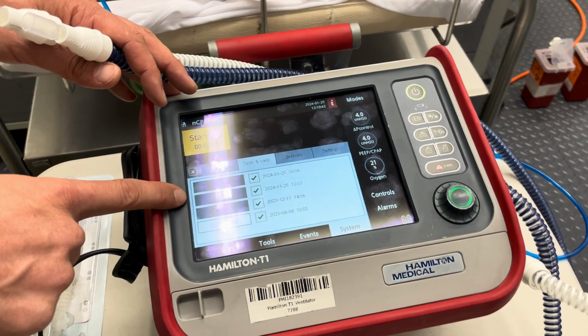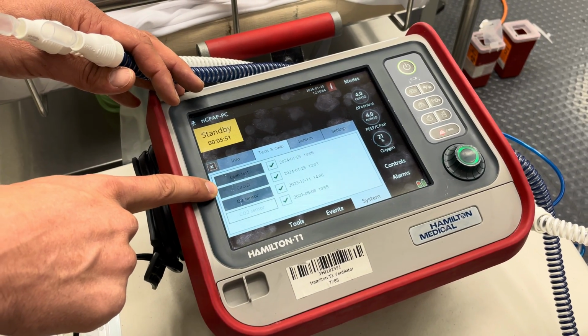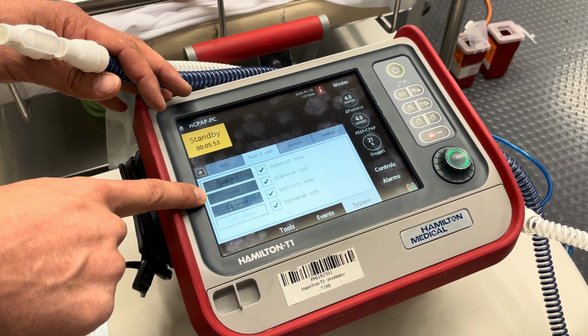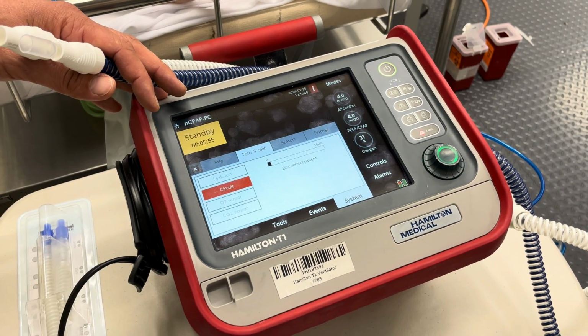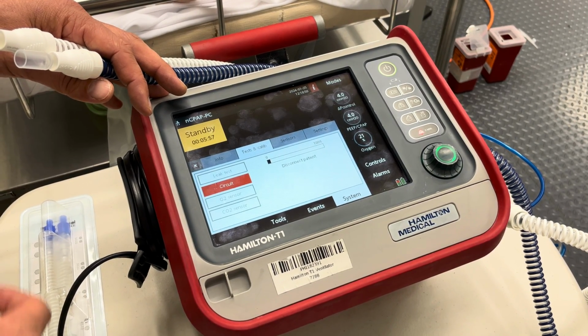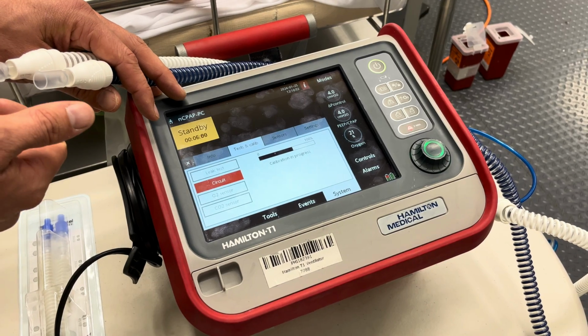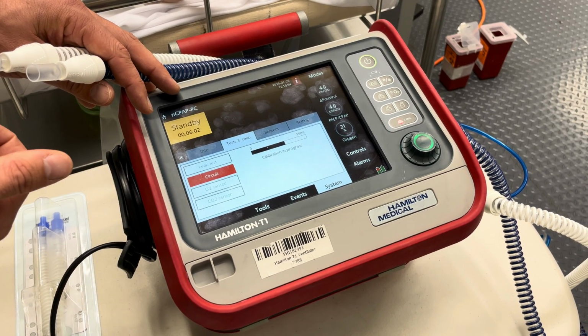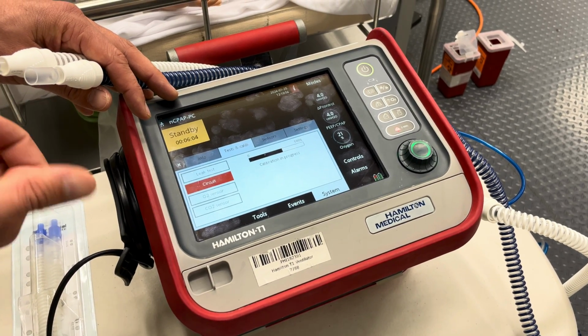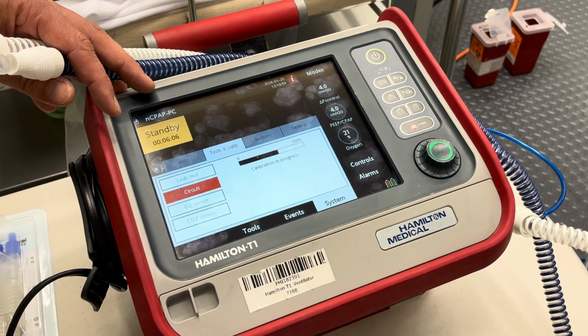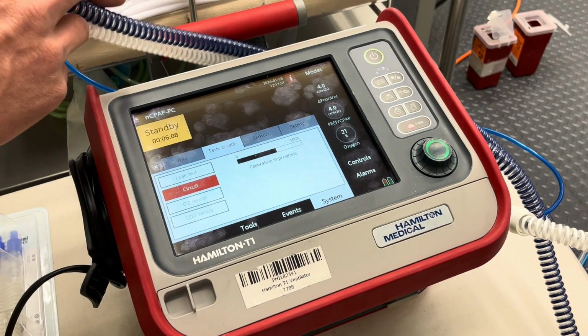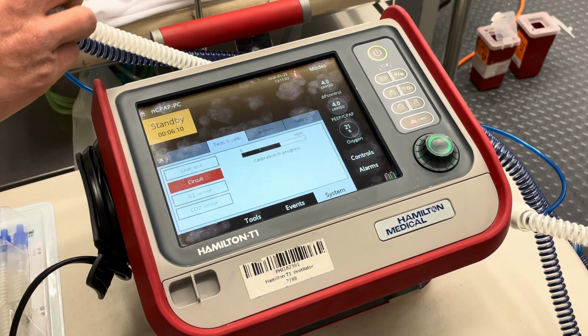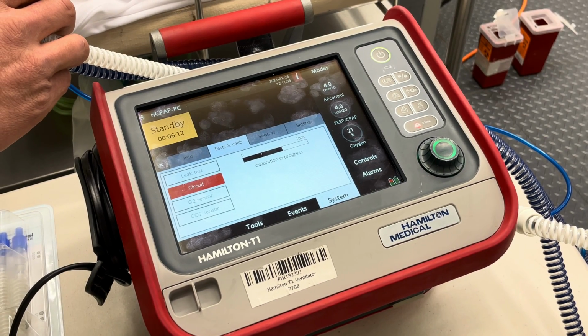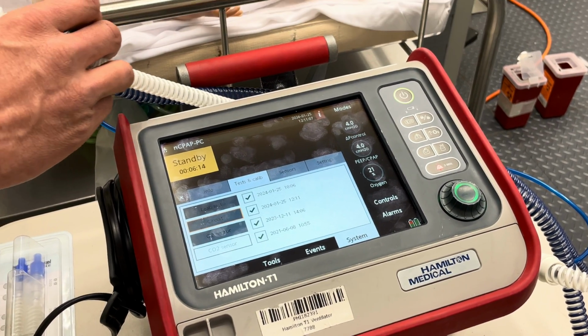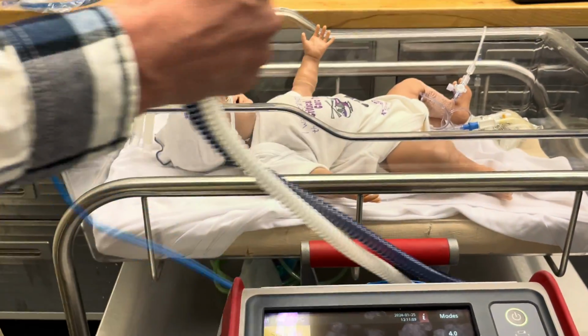When we hit confirm, the next screen it goes to is the circuit test. And you'll notice that the flow sensor test is gone. We just have a circuit test. So we press the circuit test, and we don't have to flip the flow sensor or do anything like that. It's just going to run its calibration. And when it's complete, we're ready to apply it to the patient. All right, so now that it's complete, we'll apply it to the patient.